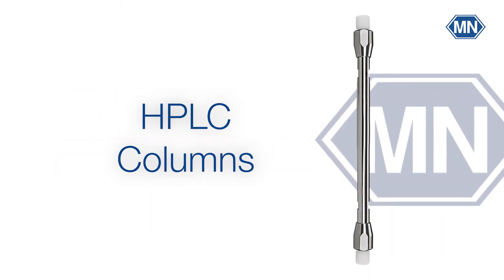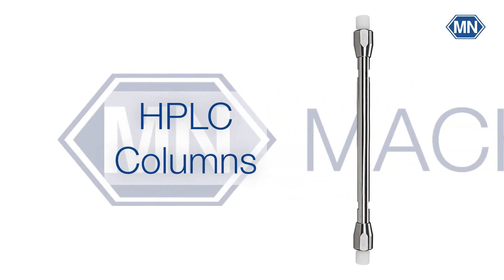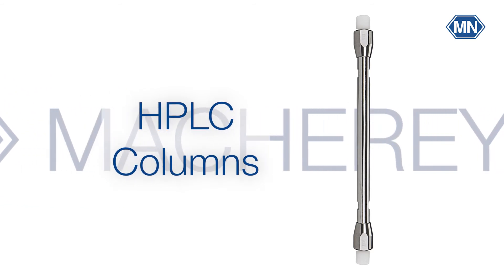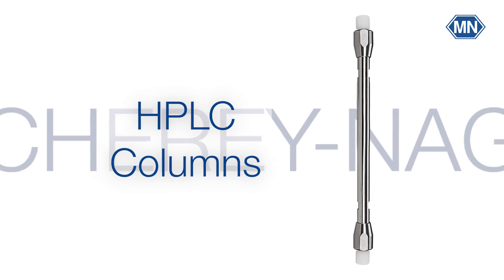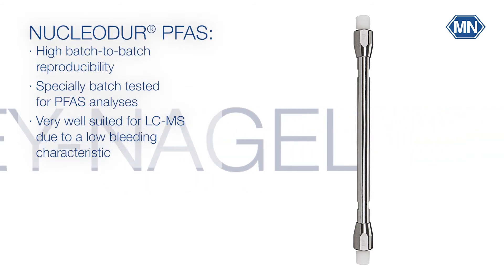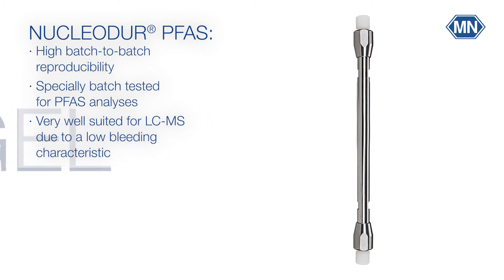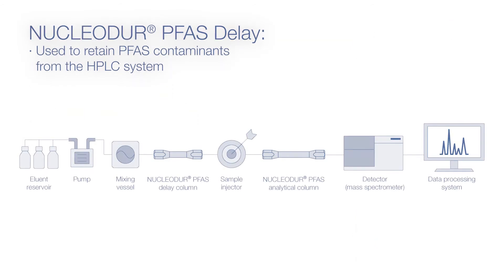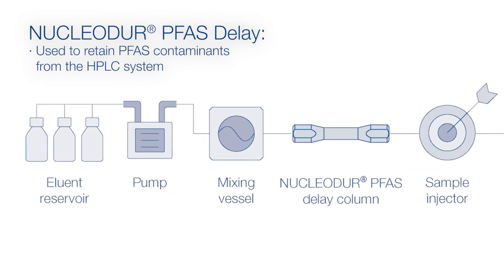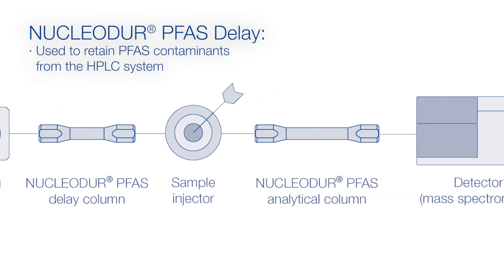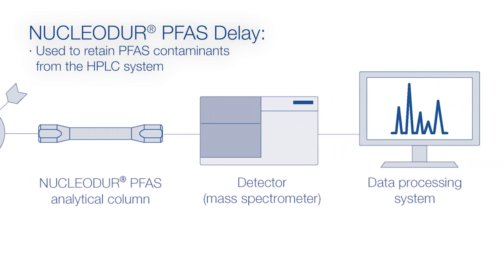HPLC columns. Subsequent chromatographic separation is often performed by HPLC. Macherey-Nagel developed for the analysis of PFAS the Nucleodur PFAS and Nucleodur PFAS Delay HPLC columns. Nucleodur PFAS HPLC columns provide a solution for analyzing PFAS substances. These columns show a high batch-to-batch reproducibility, are specially batch tested for PFAS analyses, and are very well suited for LC-MS due to low bleeding characteristics. The Nucleodur PFAS Delay column provides high retention for PFAS compounds and is used to retain PFAS contaminants from the HPLC system which could otherwise falsify the sample being analyzed. For this purpose, the Nucleodur PFAS Delay column is connected in flow direction between the mixing vessel and the sample injector.